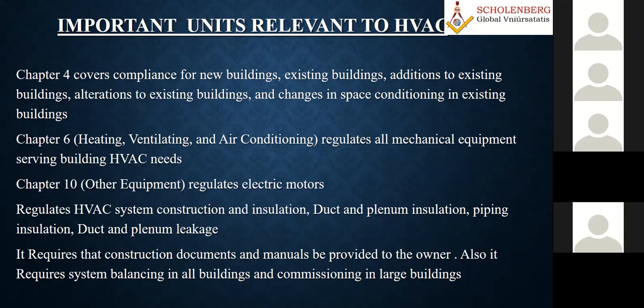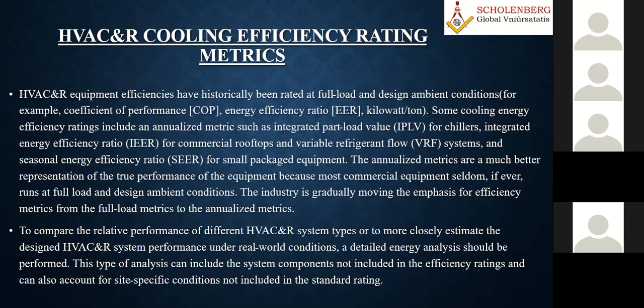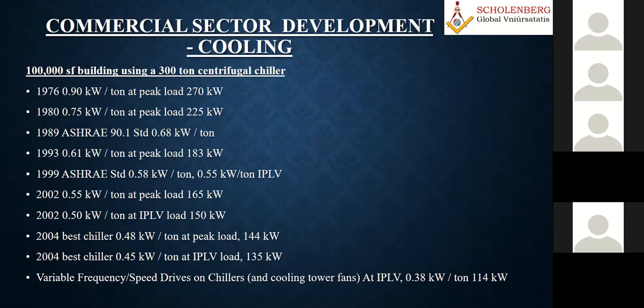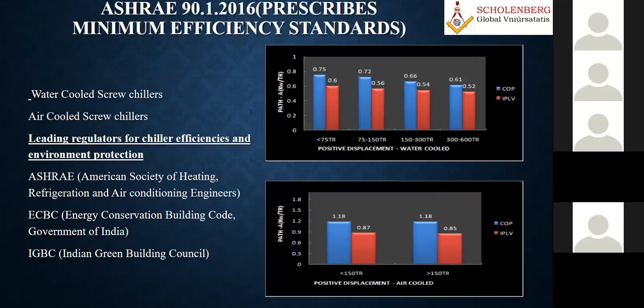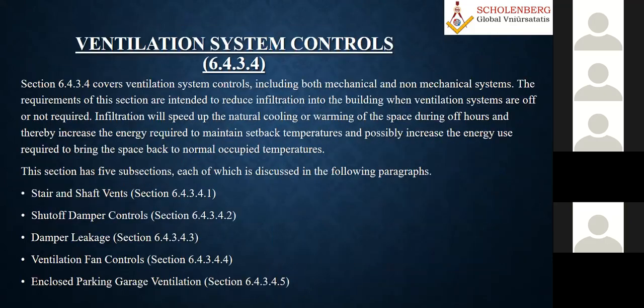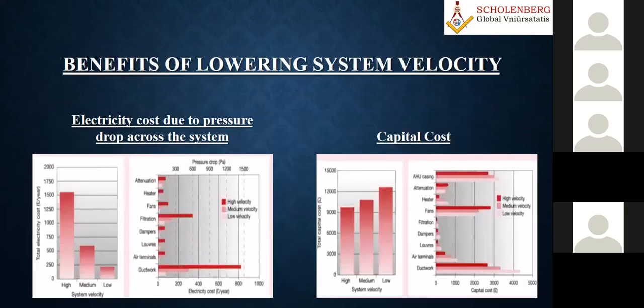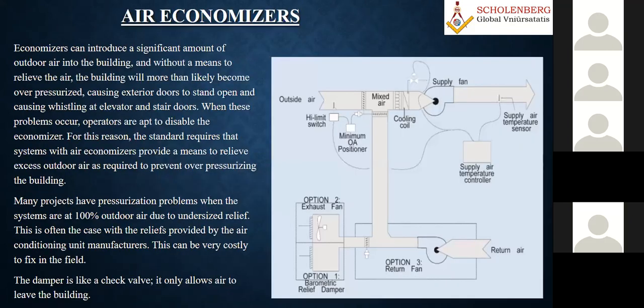Standards specify certain values, and then there are recommended values. If you are going slightly down or even slightly up, and you get a benefit during your modeling and analysis time, you can definitely take it. All the standards are only for guidance purposes and are not necessary, unless you have a legal requirement in the local building code. For example, the local code says that for a mall, you should not put your indoor condition at 19 degrees centigrade or 20 degrees centigrade.